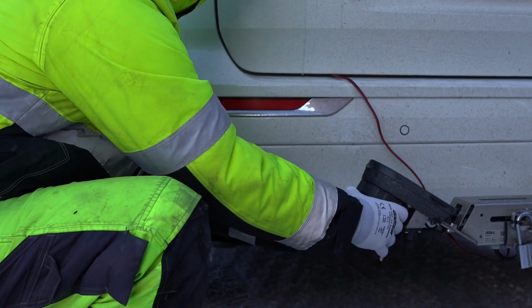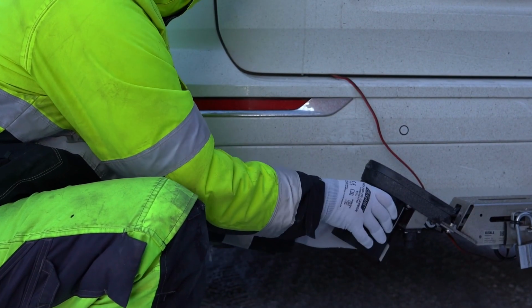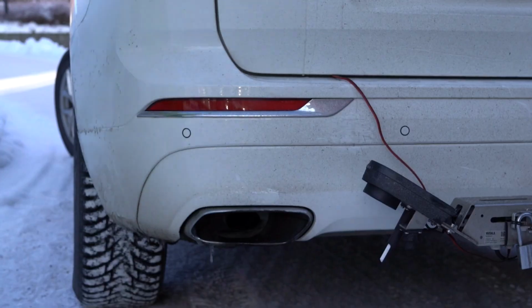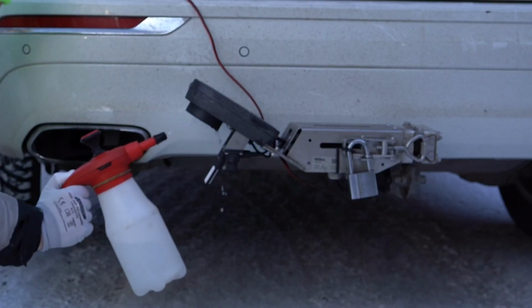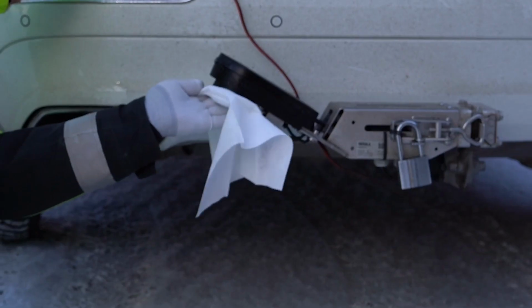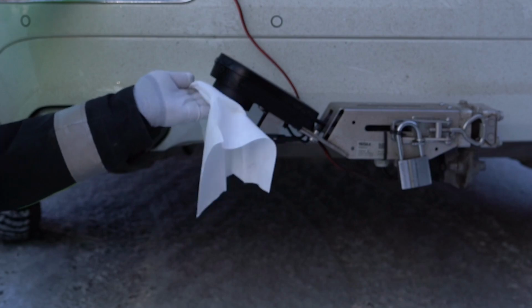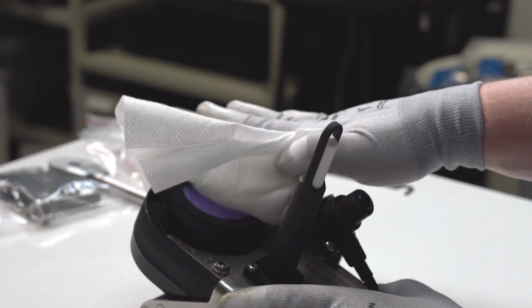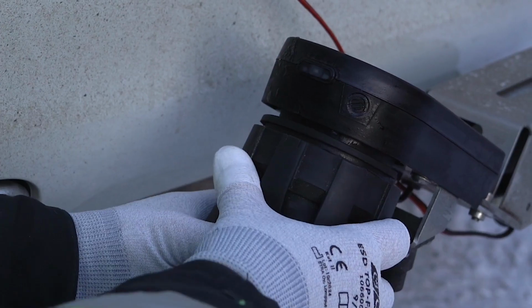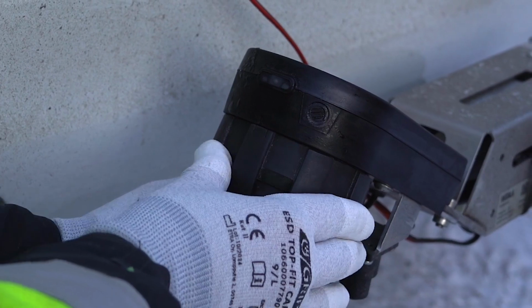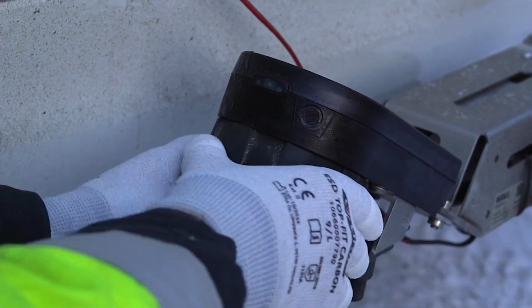Before calibration, clean the MD30 sensor window. Spray 50% isopropyl alcohol on the window and clean the window with a lint-free cloth to ensure accurate readings and optimal device performance. Clean the hood too. Check that the markings in the body and hood are aligned.